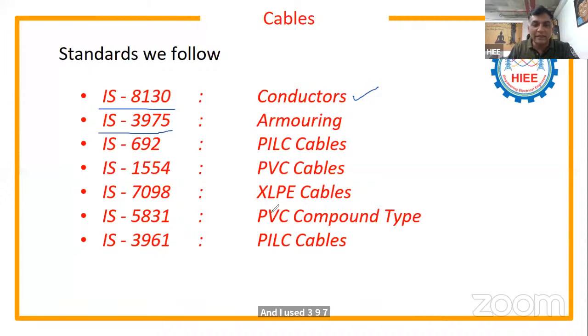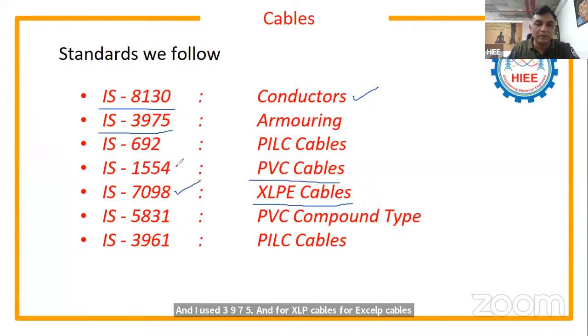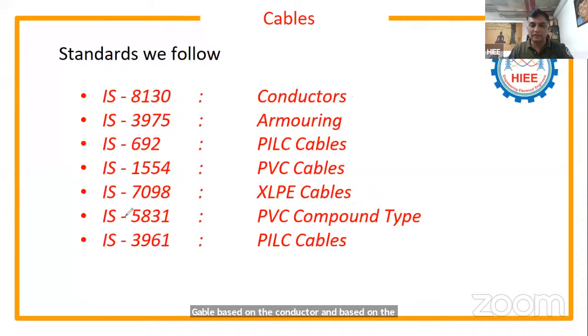And for XLPE cables, we follow IS 7098, and for PVC cables we follow IS 1554, and for PILC cables we go with IS 3961. These are the IS standards we follow for the cable, based on the conductor and based on the insulation.